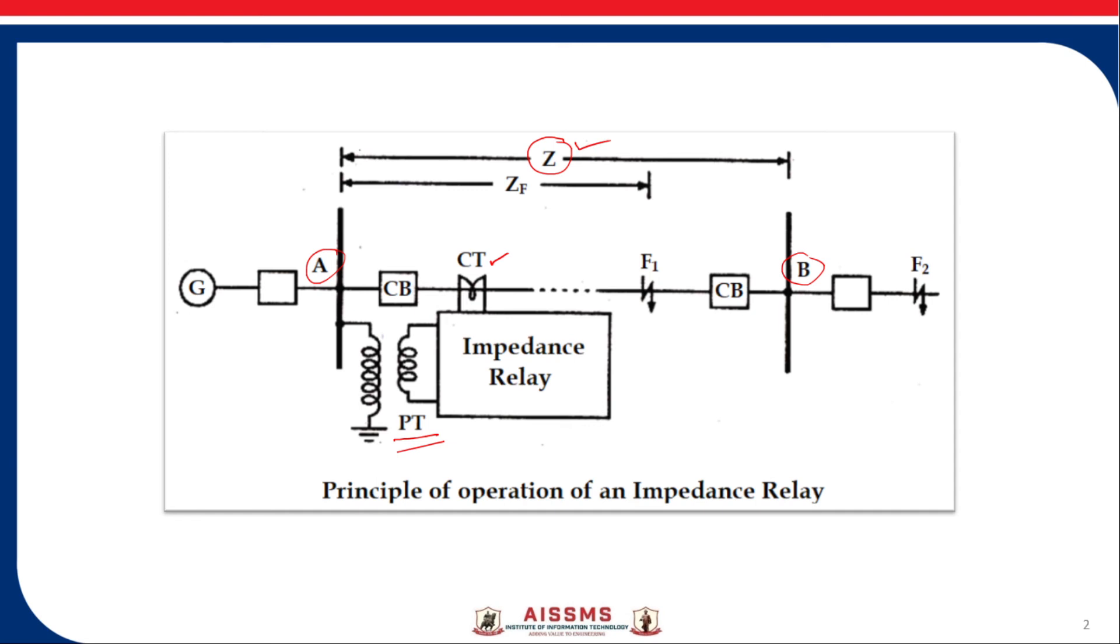Suppose the fault occurs at point F1 in the protected zone. The impedance ZF between the point F1 in the protected zone and the point of fault will be ZF. If that ZF is less than Z then relay will operate.